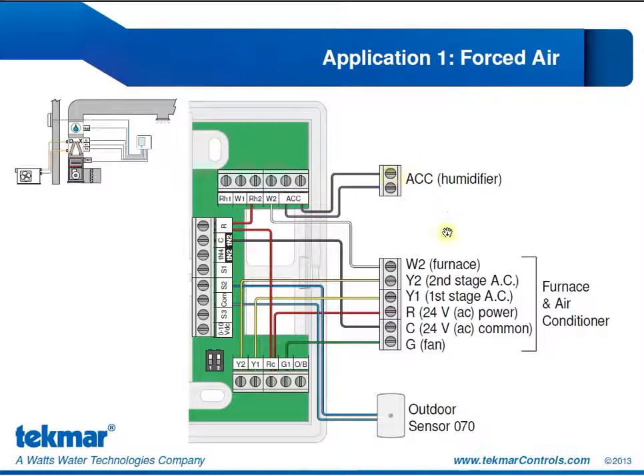Taking a look at the wiring here, we have the humidifier being enabled through the accessory relay. And then we have our connections to the furnace and air conditioner. W2 to the furnace, Y1, Y2 for the stages of air conditioning. R and C are power and common, and G for our fan.